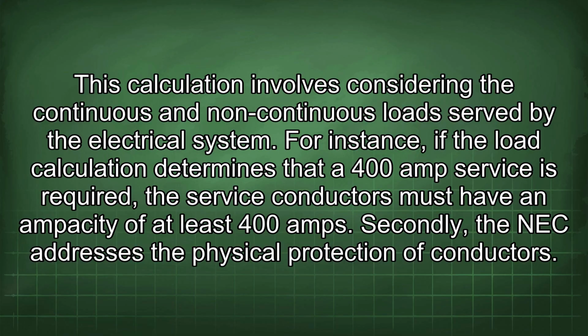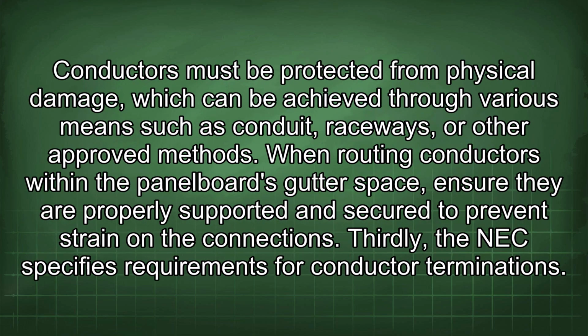Secondly, the NEC addresses the physical protection of conductors. Conductors must be protected from physical damage, which can be achieved through various means such as conduit, raceways, or other approved methods. When routing conductors within the panel board's gutter space, ensure they are properly supported and secured to prevent strain on the connections. Thirdly, the NEC specifies requirements for conductor terminations.